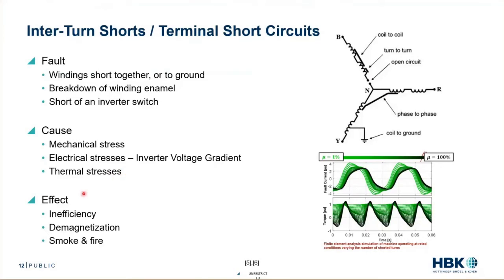The effects include inefficiency because power is not going where we want it, potentially demagnetization — which is the next failure mode we'll touch on — and in many cases smoke and fire. Here's an example: if we have a fault current with two windings shorted together, going from one percent faulted to 100 percent faulted in a given coil, we can see that the currents don't change all that much, but even a small fault creates a torque disturbance, and a large fault creates a very large torque disturbance. So you're now experts on inter-turn shorts — stator windings get shorted together, creating large unwanted currents and heat.